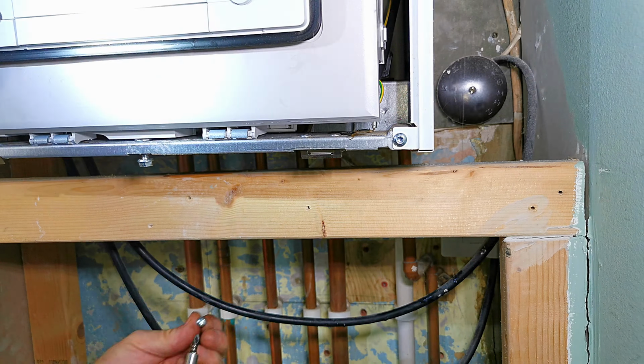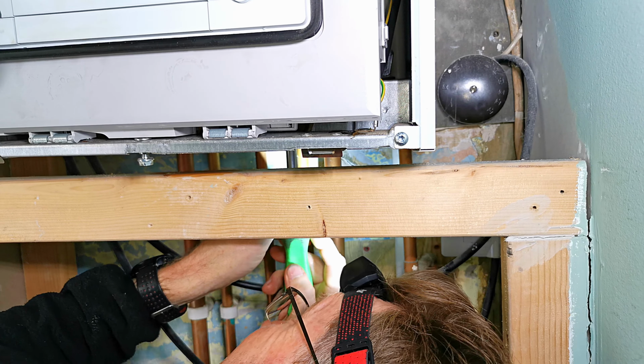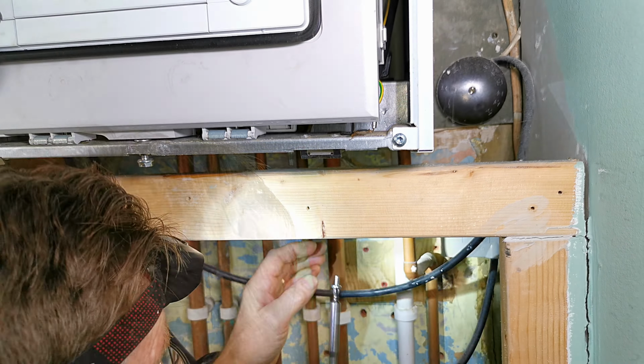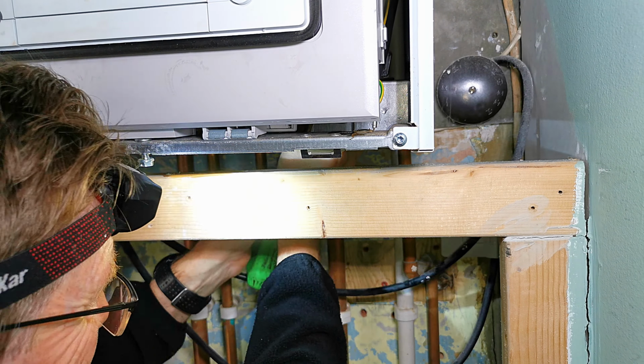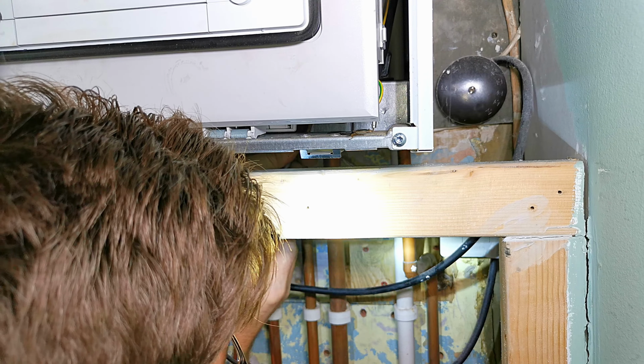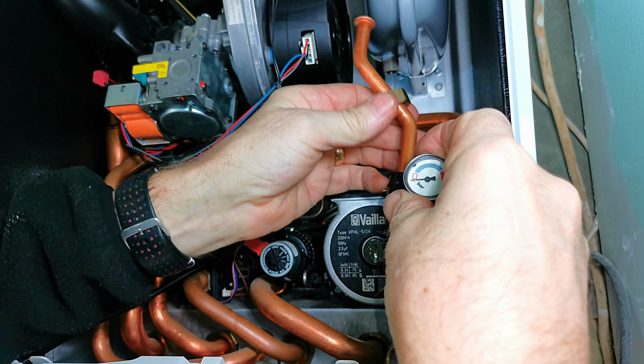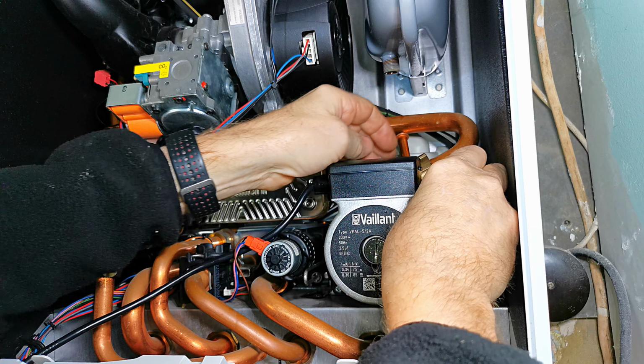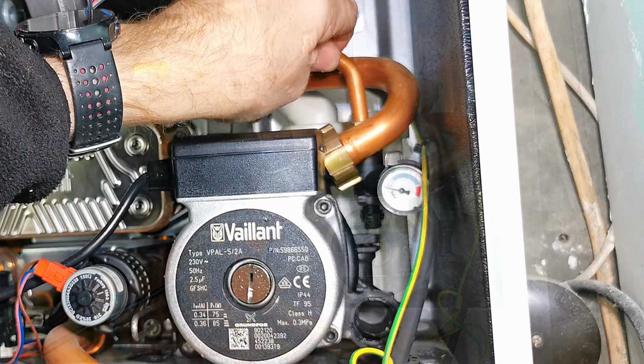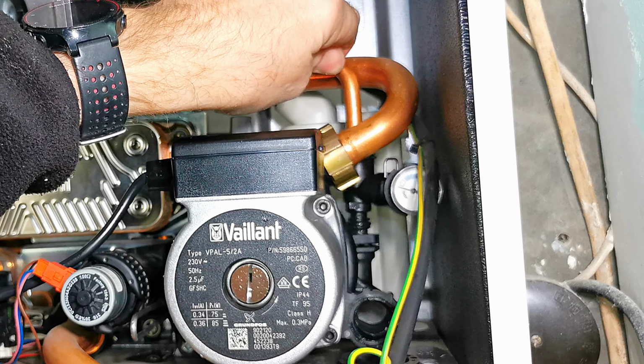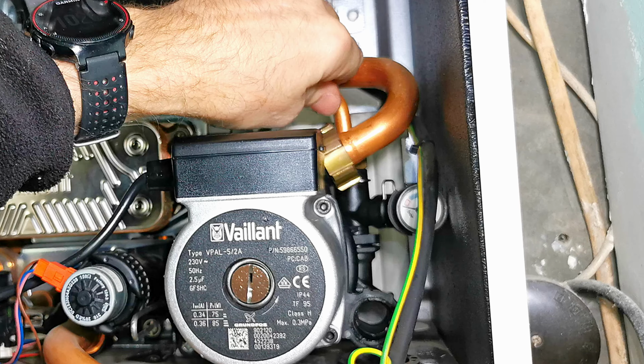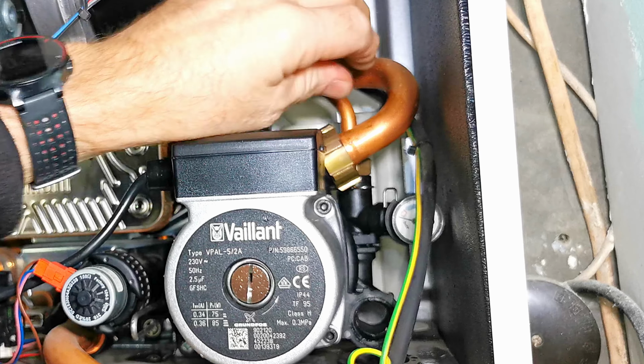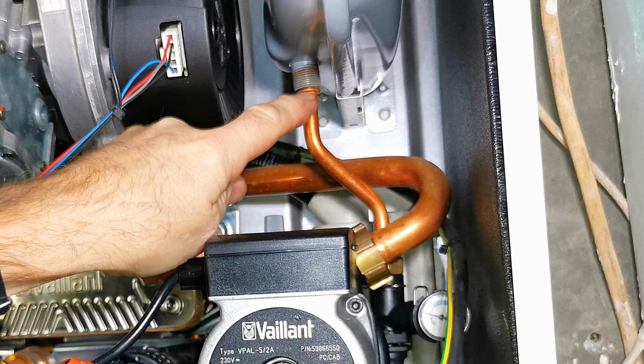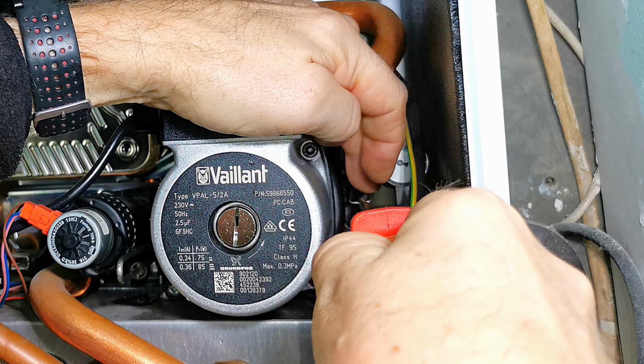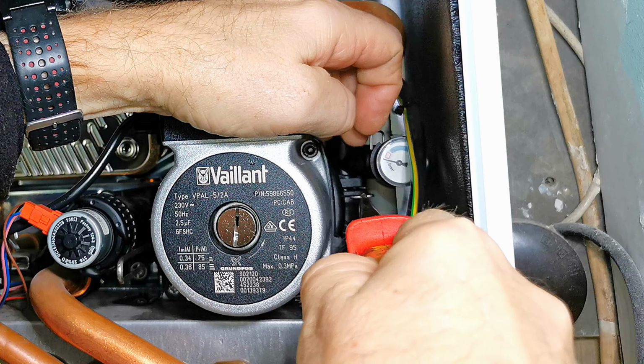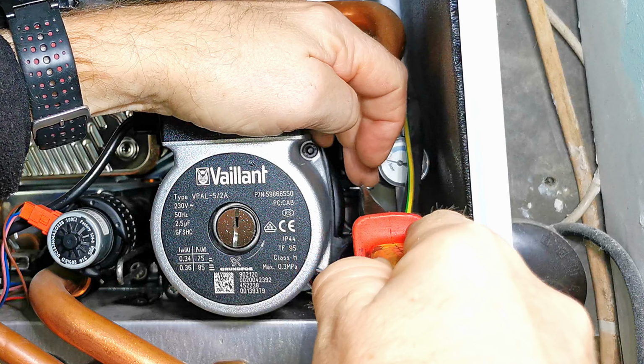So that's that done. I'm now going to go underneath the boiler and fit those 2 screws back into the pump bracket. That's one done, and now fit the second one. I'm going to do up both these screws nice and tight and lock the pump into its final position. I'm now going to refit the expansion pipe and pressure gauge. So slip it in underneath that pipe, then drop it down into the pump housing like that. Give it a good old push and make sure it fits right down inside. When it's in the correct position, the expansion pipe should line up with the bottom of the expansion vessel, like that. I then use my long nose pliers to hold the clip so I can insert it into the pump housing, which will then lock the pressure gauge into its position.